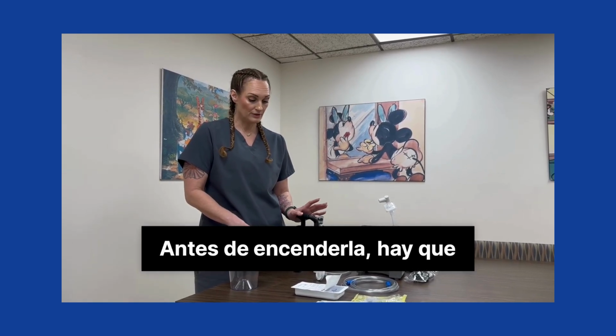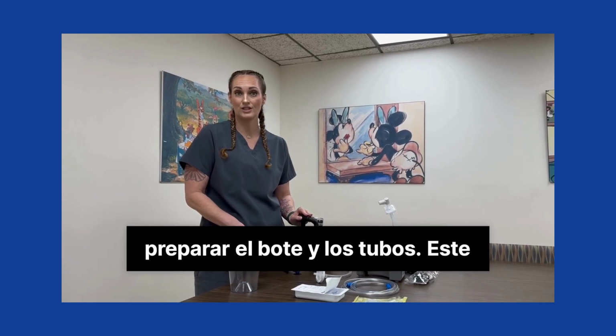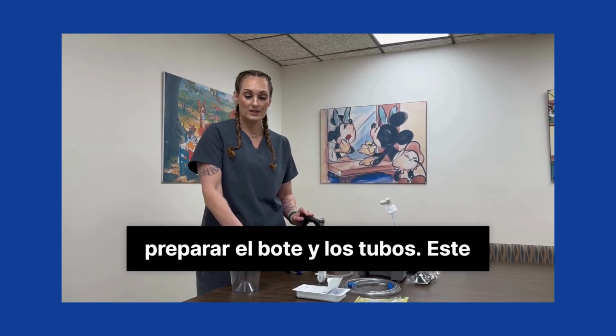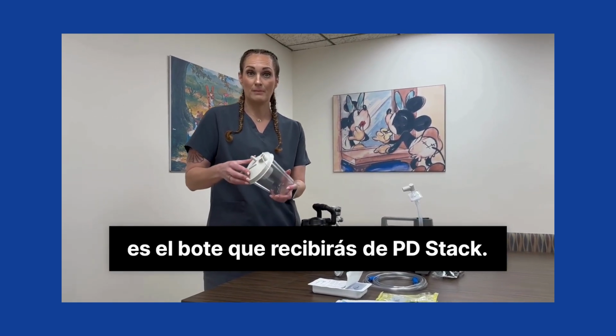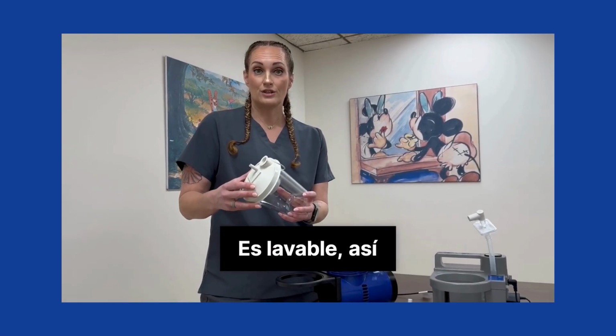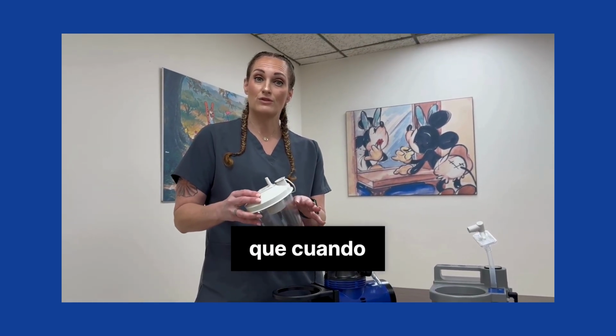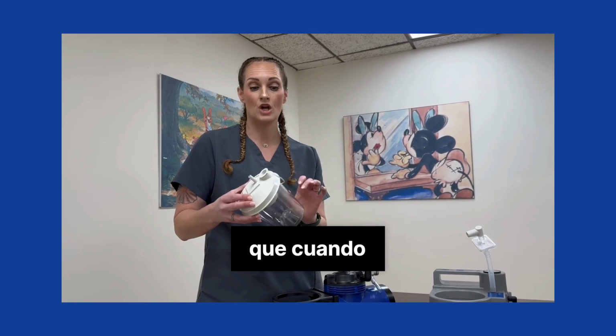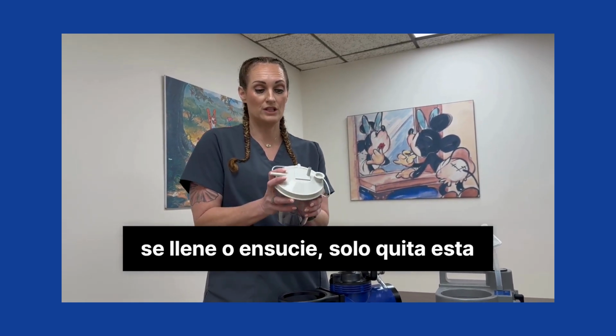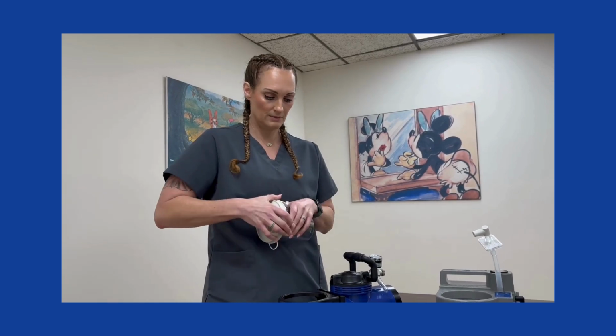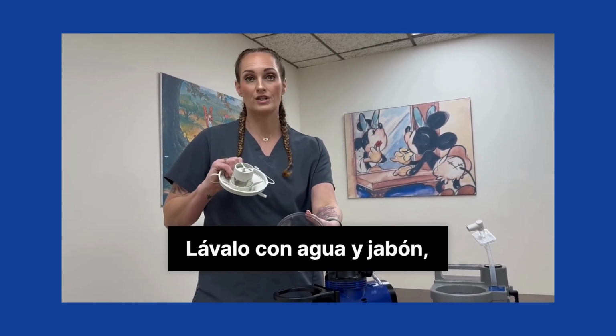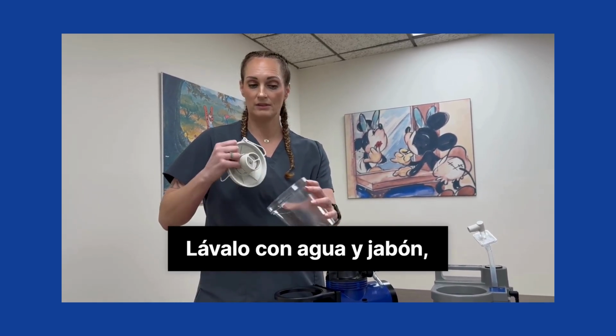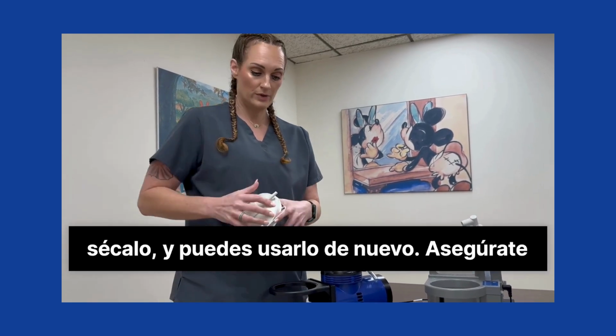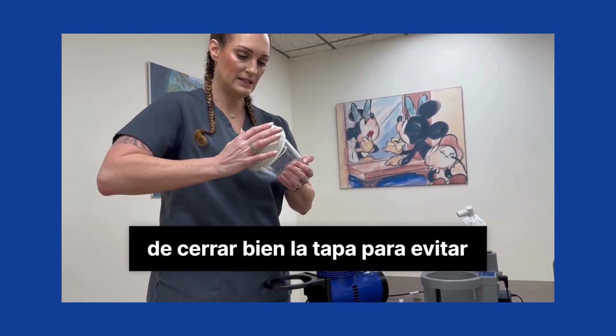Before you turn the device on, you want to set up your canister and your tubing. This is the canister you will receive from PD-Stat. It's washable, so whenever it gets full of secretions or dirty, just pop off the top, wash it with soap and water, dry it out, and you can use it again. Make sure you pop it back on completely so there's no air leak.